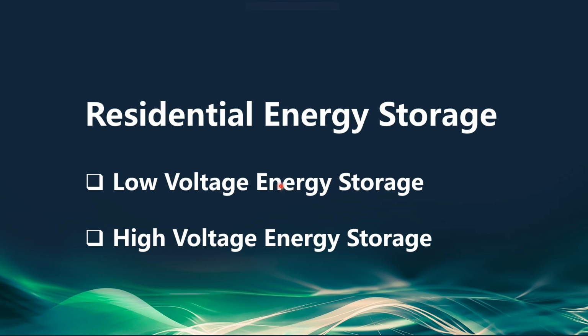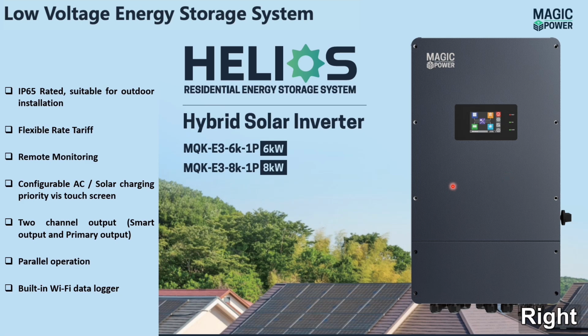So first we learn about the low voltage energy storage system, the series called Helios series. The rated output power for the system is 6 kilowatt and 8 kilowatt. If we look at the key features of the system, the system is IP65 rated, making it suitable for outdoor installation, flexible rate tariffs, remote monitoring through application, configurable AC and solar charging priorities via touch screen, two channels output, the smart output and primary output.